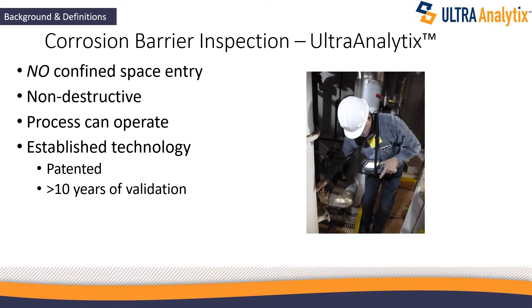UltraAnalytix performs a different kind of corrosion barrier inspection. Here we actually see a photo of an inspector placing an ultrasonic transducer. Using a conventional off-the-shelf ultrasonic flaw detector and saving a reading by following a special procedure, that saved reading can then be used to evaluate condition at that location. You can take more readings and determine a better global overall picture. This is non-destructive — the process can continue to operate, usually with no reason to shut down. It's an established, patented technology that has had over 10 years of validation.